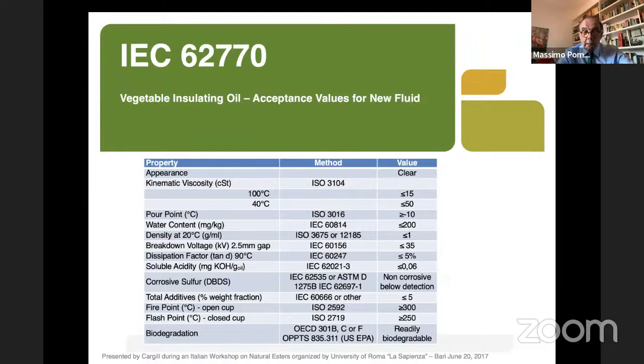And of course, the standard report is number for two different temperatures, at 100 degrees or 90 degrees and 40 degrees. And of course, we are looking with much more interest the performance of kinematic viscosity at higher temperature, when it's much important to exchange it, because we have to remove the heating from the transformer.